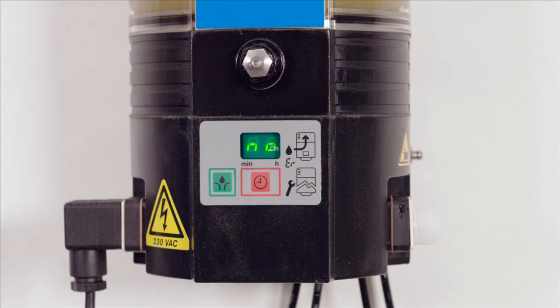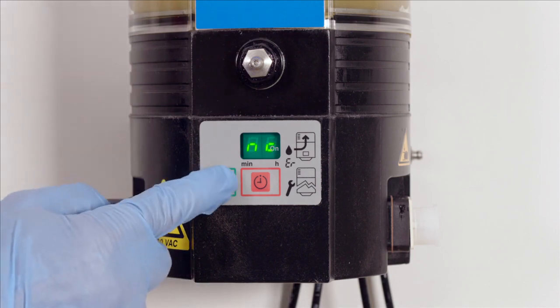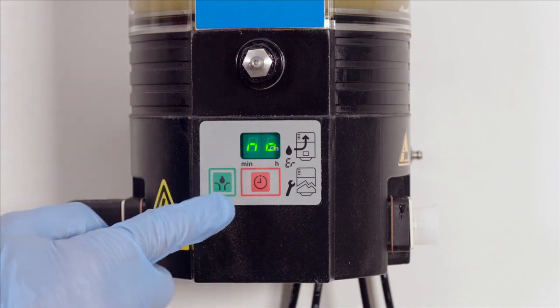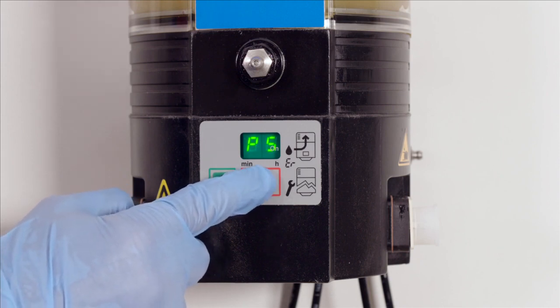In P4, the type of output signal can be set to either NC for normally closed contact or NO for normally open contact. Select with the green key. Then press the red key to confirm and move to the next step. P5 is now displayed.